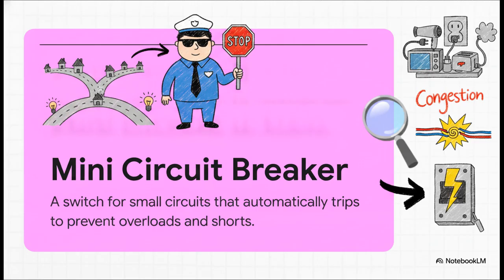Congestion is basically an overload. That happens when you gradually plug in way too many heavy appliances on one single circuit. A pileup is a short circuit, like when a phase wire directly touches a neutral wire. That creates an instantaneous, massive spike in current that generates a magnetic field inside the MCB, forcing it to trip immediately to protect the whole system.